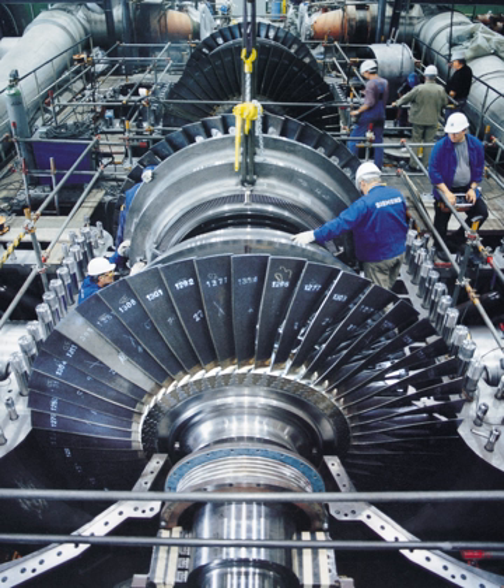This reactive power can be provided by the generators themselves, through the adjustment of generator excitation, but it is often cheaper to provide it through capacitors. Hence, capacitors are often placed near inductive loads to reduce current demand on the power system, i.e., increase the power factor, which may never exceed 1.0, and which represents a purely resistive load.